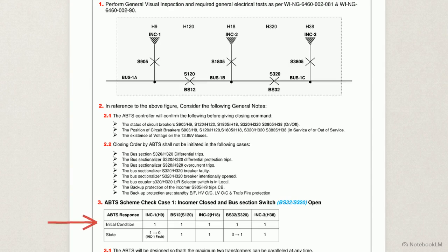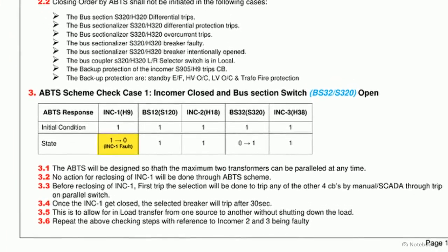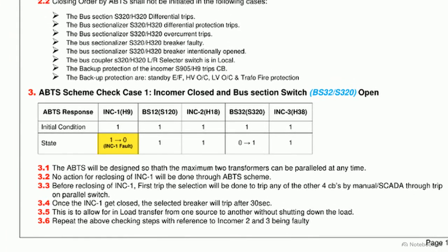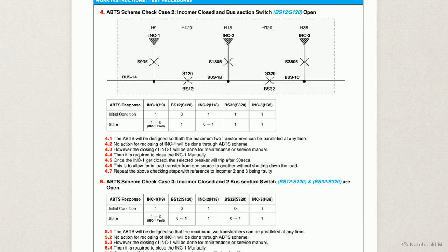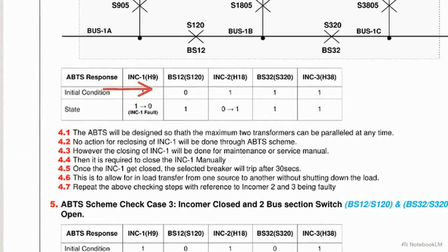3 incomers are closed. The bus section switch is open. Simulating a fault changes the state to 0. If closed manually, ABTS automatically trips it after 30 seconds, maintaining parallel limits. Looking at Case 2 and 3 tables, we test how transfer logic adapts to different configurations.